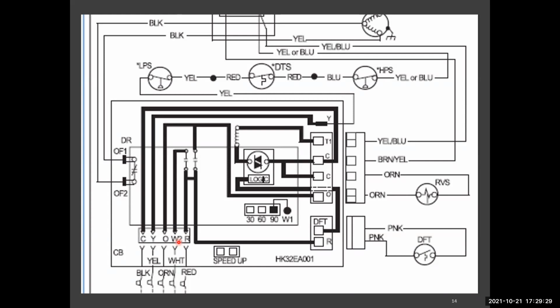So if we already see that, hey, defrost is initiated, we heard it come over, and now we go in and find out we don't have any resistance heat, or the gas furnace is not coming on, we can come back and check and see if this contact is open or closed. Same thing if a reversing valve does not make, we can see if we have 24 volts to it. If we do, then we can go ahead and isolate it, ohm it out, see if our coil is open. And that's why you find that in most of our training we include a lot of the sequence of operation.